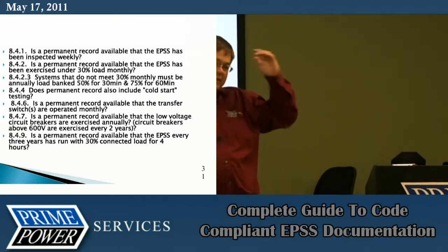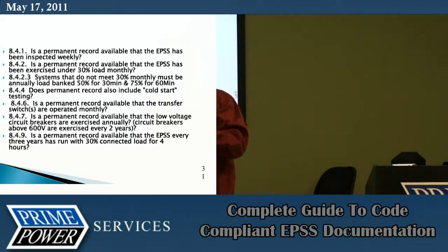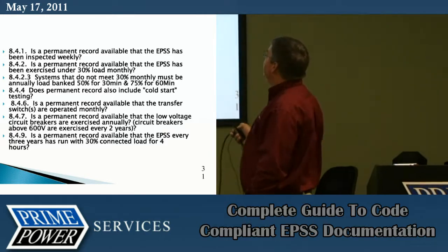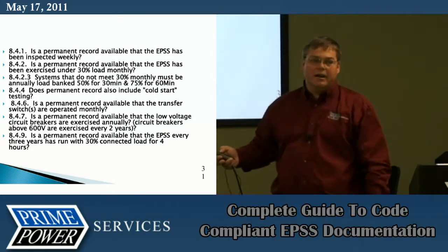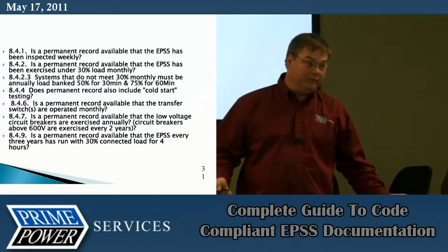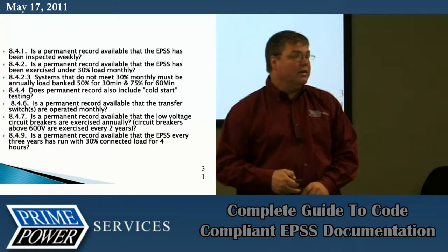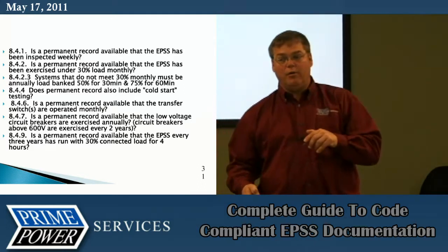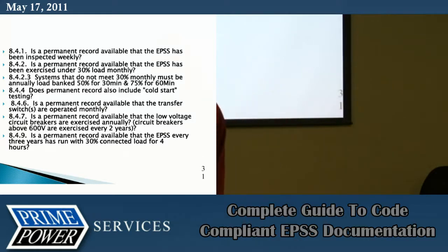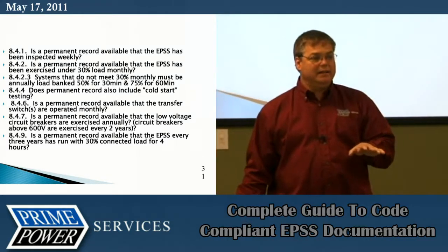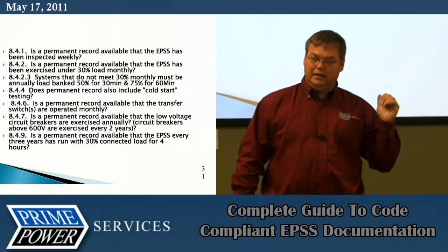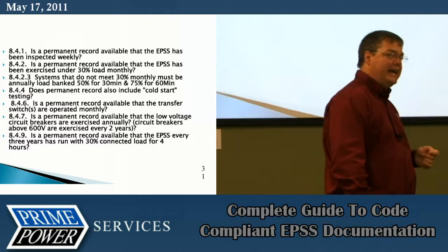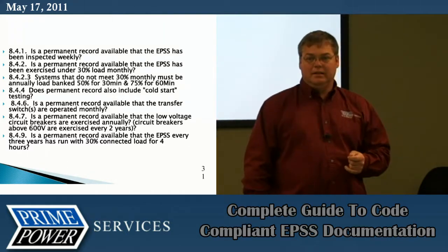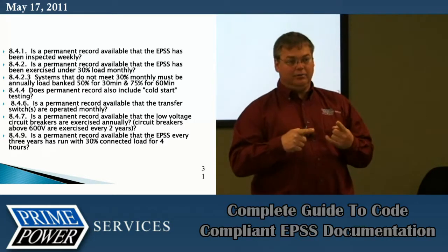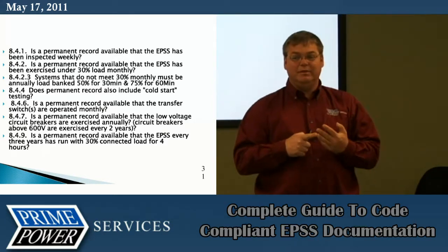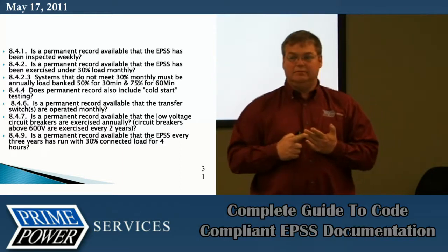on the slide back when it talks about the 30% monthly run to 20 to 40 days, here's the difference. NFPA says monthly. It's still the same code. 20 to 40 days is monthly, any way you look at it. What the Joint Commission surveyors will do, and I happen to know on the property management side and the industrial side, if at some point in time you get inspected by the state, they're going to follow the same code. And what they want to see is 12 months worth of data that this generator has been tested. They're going to look at the date, they're going to look to see what the load was, and there needs to be some type of time marking on your sheet.